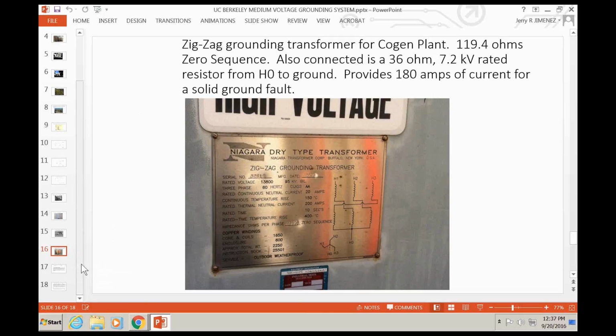Well, Mr. Ship. Actually, as I'm sure many of the universities do, we have some pretty modern protective relays. We happen to have these Siemens SIPROTEC relays. They've got really good fault recording in them, so I've got lots of records. The grounding that we have has no effect on any phase-to-phase faults. In fact, what I can see on many of the faults we've had is that sometimes the ground fault doesn't last very long, and it becomes a phase-to-phase fault or a three-phase fault.